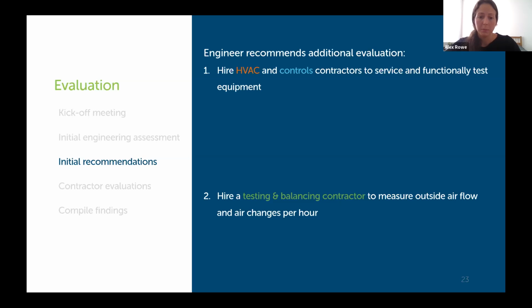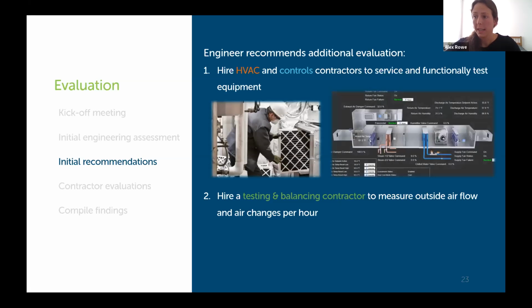So the engineer then recommended that the customer pursue some additional evaluations. First, they recommended that they hire HVAC and controls contractors to service and functionally test equipment. And then they recommended that the customer hire a testing and balancing contractor to measure outside airflow and air changes per hour in the way that the HVAC system is currently operating.